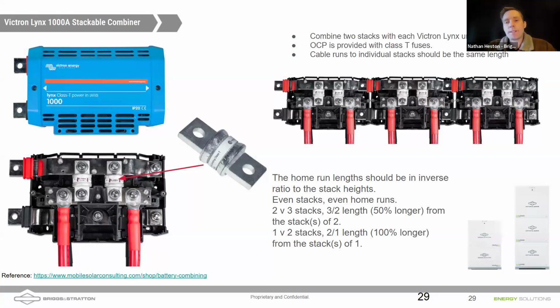Well, what you overall want is the resistance of that section of the circuit to balance with the resistance of the section with 2 batteries. The more batteries you have in parallel, the lower the overall resistance is. So you would use a slightly longer cable with the 3 stack of batteries, and a shorter cable with the 2 stack of batteries, which helps balance the power draw out of the 3 stack and the 2 stack.